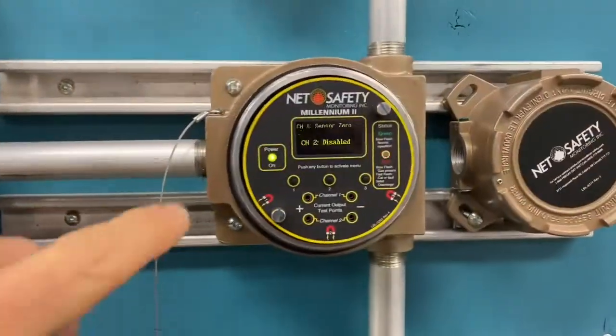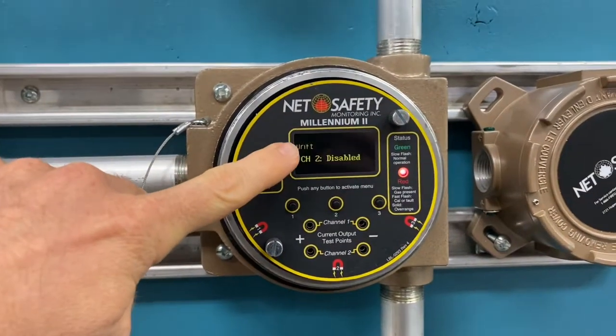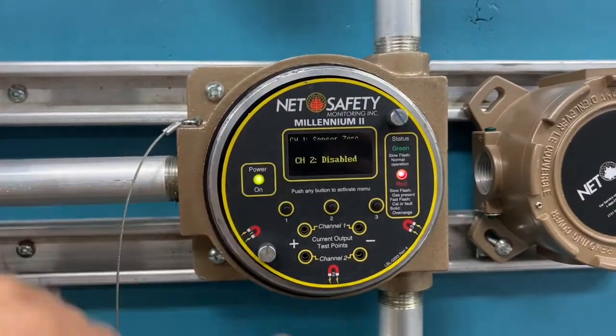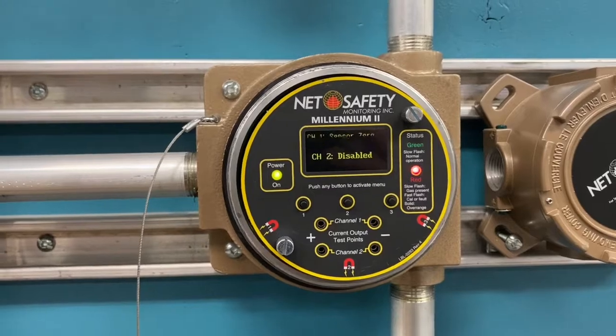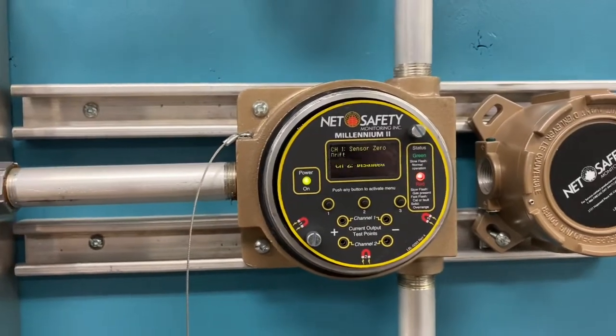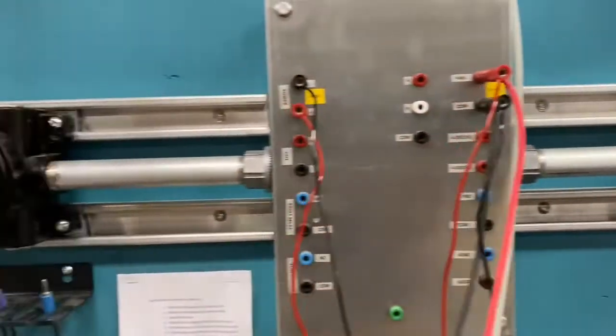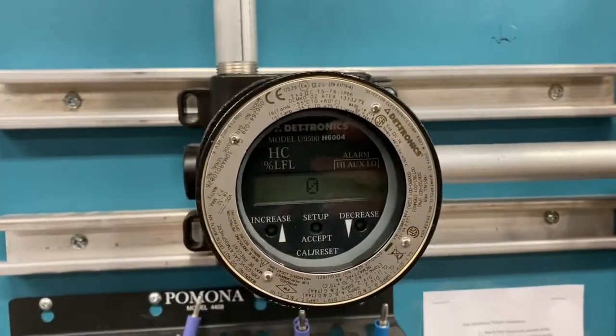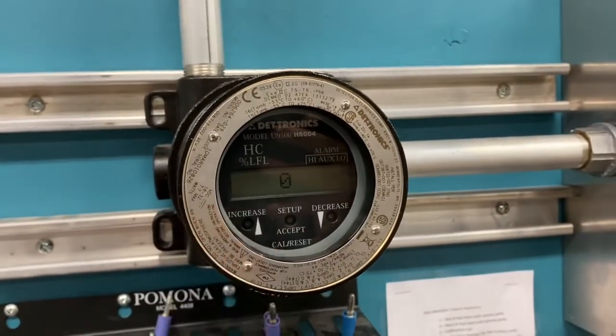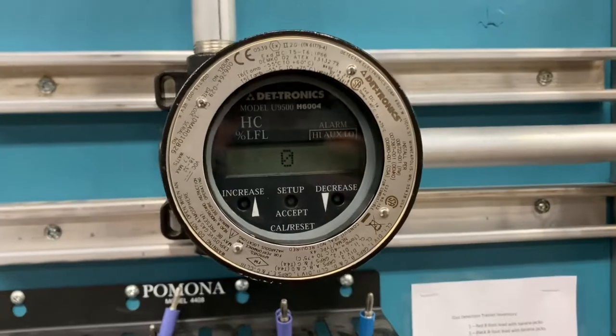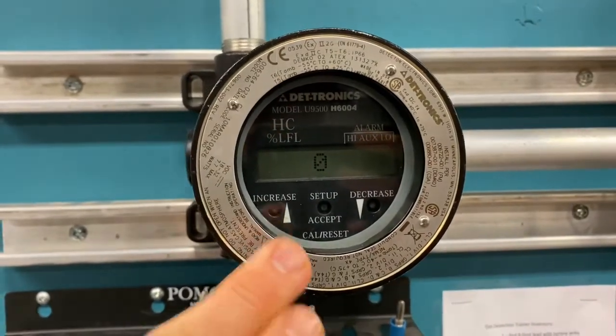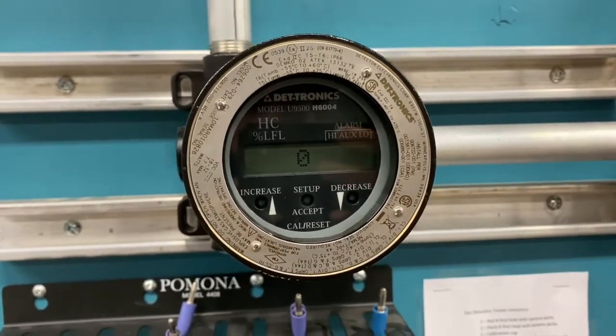All right, so now I have channel 2 disabled and channel 1 enabled, but you can see that it's giving us this sensor zero drift, likely because the system hasn't been used in probably close to a year. The other thing that we wanted to have a peek at here is now it's been about 5 minutes or so, and you can see that the Det-Tronics system right here is reading 0. So everything looks good there.